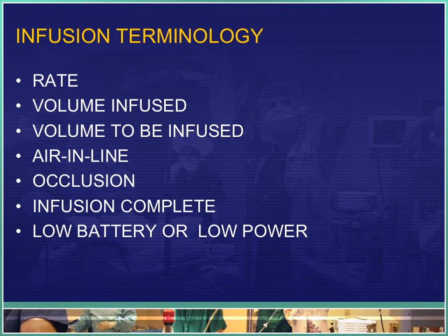Air in the line is designed to detect air in the line and may include air detection and air removal. Occlusion detects absence of fluid flowing upstream between the pump and the infusion container, or downstream between the patient and the pump. Infusion complete is an alarm triggered by a preset volume limit. And low battery or low power gives the user ample warning of the pump's impending inability to function.